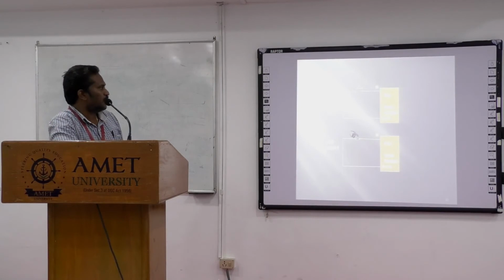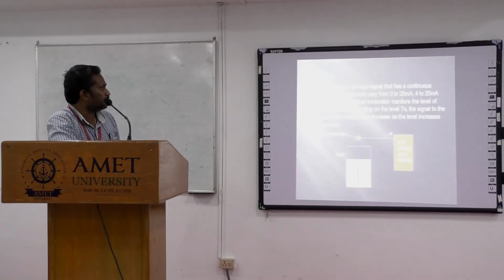So here you will see the logic, off logic. When the switch is open, the logic is 0, which means off, the switch is off. The PLC input module is 24 volt DC, so there will be no voltage to the PLC input module. The second one is NC, so NC means closed condition. When you press the switch it will be closed, so it becomes a logic 1. Here it is an NC switch. So with logic 1, the 24 volt input will be sent to the PLC input module.